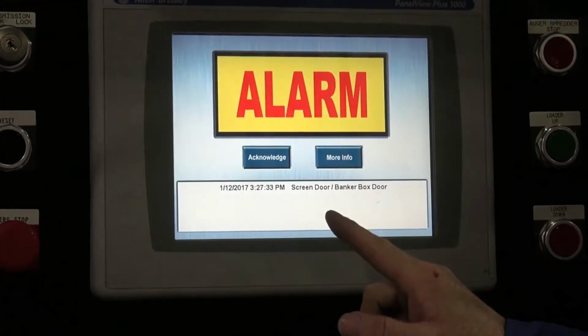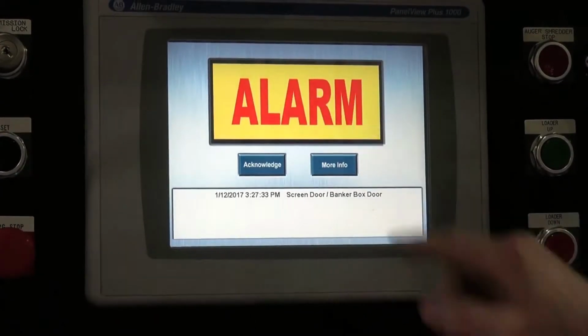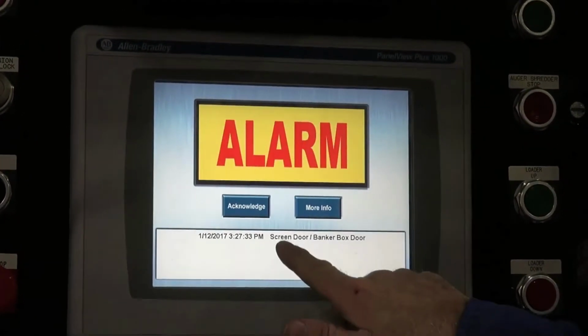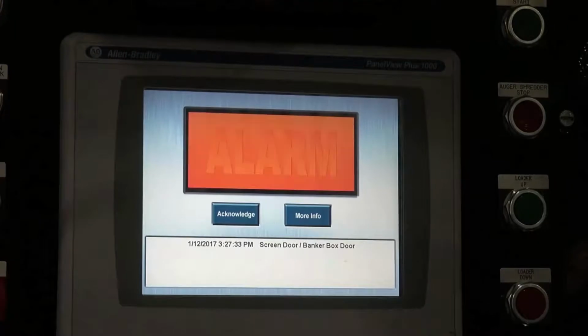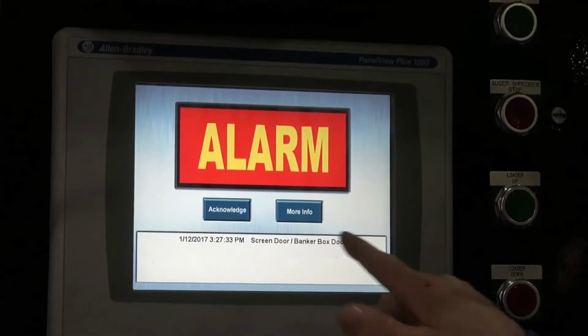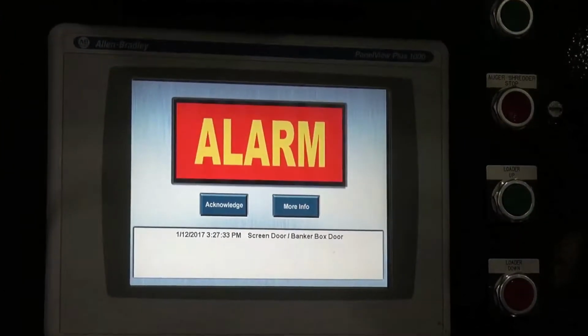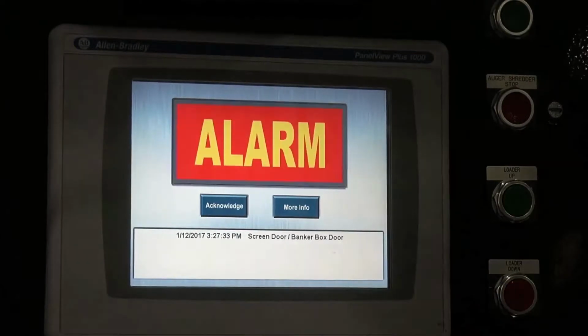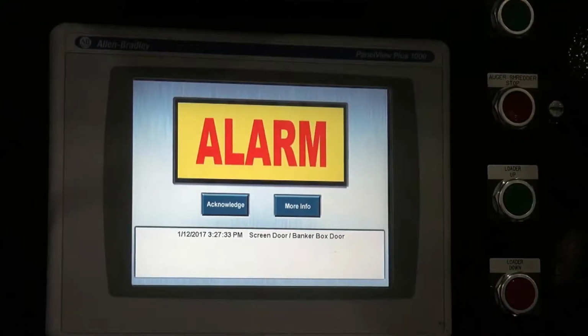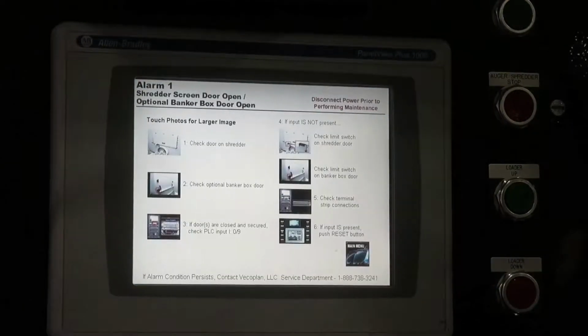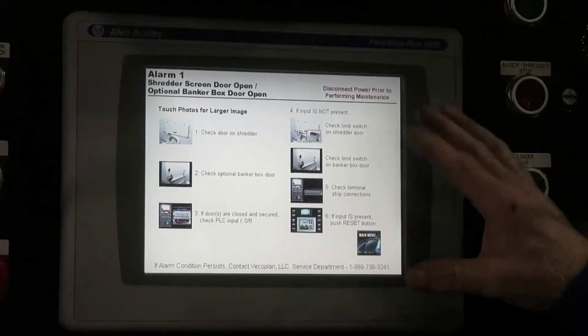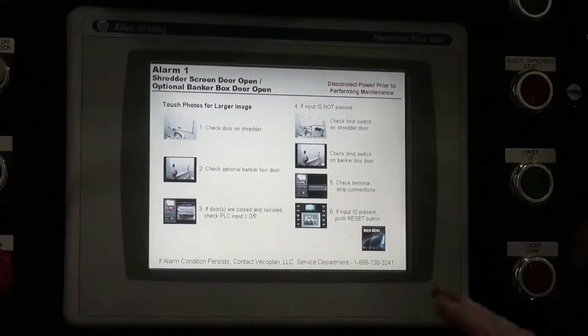When the fault occurs, the main screen will go to the alarm screen. The alarm screen will tell you what the fault is. In this case, it says screen door banker box open. We can acknowledge it and clear it, or we can ask for more information. When we ask for more information, this screen will bring us to the flow chart to help us diagnose.